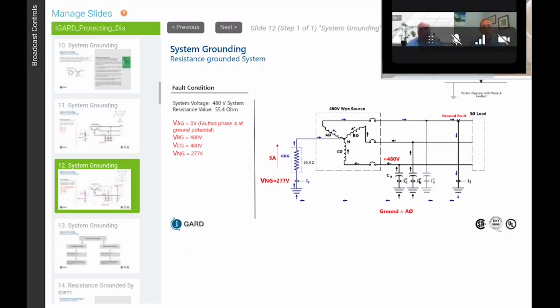So you always have to check your TVSS is suitable for use with the resistance grounded system, and your variable frequency drives are suitable for use with your resistance grounded system. The other thing you have to check for is that with the resistor monitoring, not all resistor monitoring devices on the market can accommodate YY connected PTs that are downstream from the transformer. So they may not necessarily work. And they may have difficulty with multiple sources.